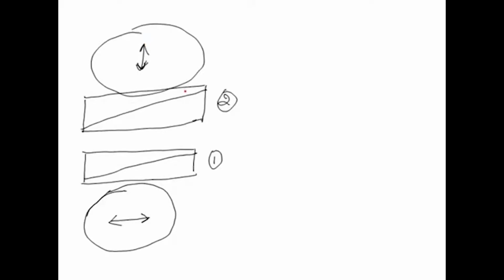Now, when the polarizer and analyzer are at 90 degrees, or perpendicularly oriented to each other, they are called crossed, because any light which passes through the polarizer will not pass through the analyzer. So, now let us see how DIC microscopy works. In this particular one, the first prism is the prism just above the condenser lens.